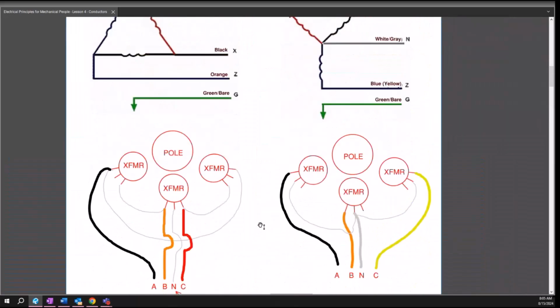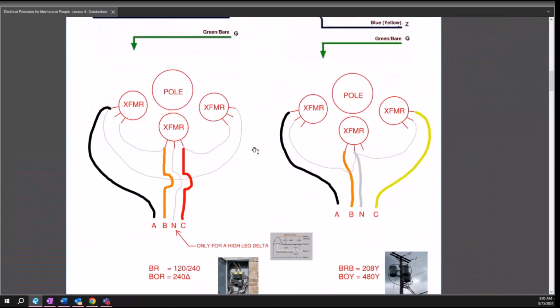One thing you can always rely on is looking at poles with 3 transformers, you can actually tell how these are wired just by looking. Whenever the corners are connected together like this, all the corners connected, that's going to be a delta, period. You can't get 208 or 480 out of that. By the same token, if you see all the middle tabs connected, that's going to be either 208 or 480 Y.